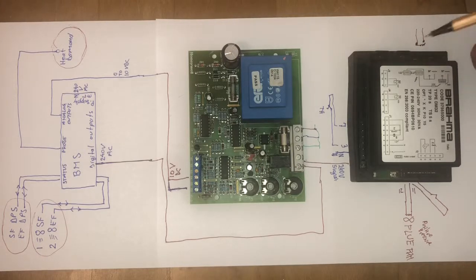When you open the valve, the gas will pass through this zap, through this blue flame, and the flame will come on. When the flame comes on, you'll hit the ionization probe, and if the ionization probe is okay, it will send an input to the Brahma controller, and the Brahma will know that we have flame. It's an electrical input, so it will be half-wave rectified, which means through the flame you'll have an electrical impulse into the ionization probe, and that input will go back into the Brahma, and Brahma will know that you have a good flame. If you have a good flame, this is it.